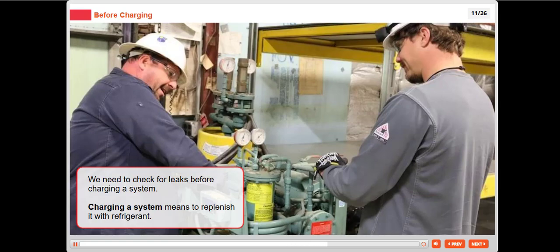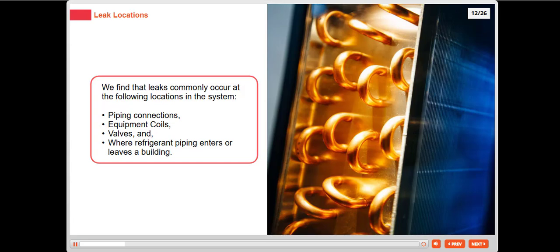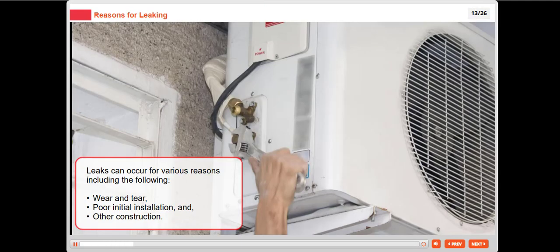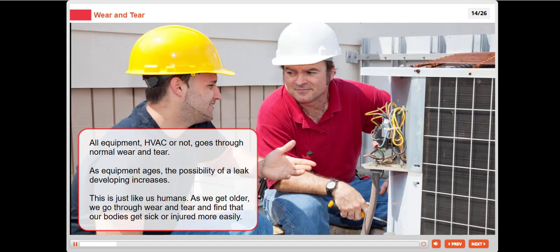We find that leaks commonly occur at the following locations in the system: piping connections, equipment coils, valves, and where refrigerant piping enters or leaves a building. Leaks can occur for various reasons including the following: wear and tear, poor initial installation, and other construction. All equipment, HVAC or not, goes through normal wear and tear. As equipment ages, the possibility of a leak developing increases.